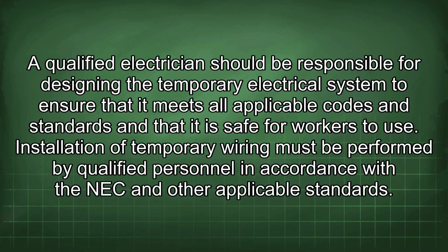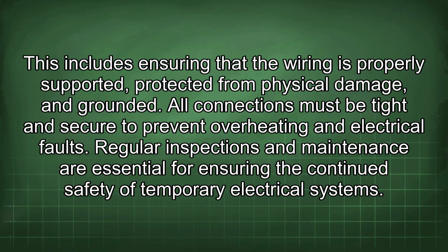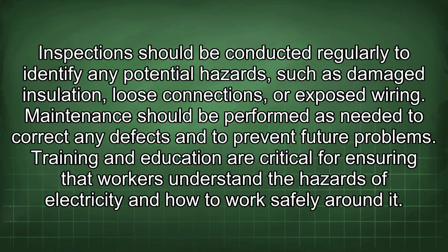Installation of temporary wiring must be performed by qualified personnel in accordance with the NEC and other applicable standards. This includes ensuring that the wiring is properly supported, protected from physical damage, and grounded. All connections must be tight and secure to prevent overheating and electrical faults. Regular inspections and maintenance are essential for ensuring the continued safety of temporary electrical systems. Inspections should be conducted regularly to identify any potential hazards, such as damaged insulation, loose connections, or exposed wiring. Maintenance should be performed as needed to correct any defects and to prevent future problems.